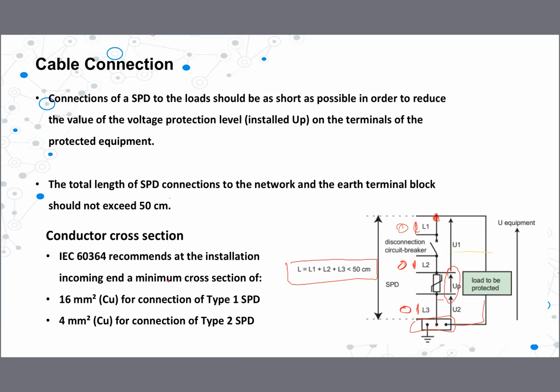Then according to IEC 60364, for type 1 SPDs, the cable size should be 16. For type 2, you can use 4 millimeter square copper. If it is copper, 16 for type 1, right? So this is a very important point, your cable length. If you exceed the cable length, you will not get an effective protection level. Your UP will be affected, right?